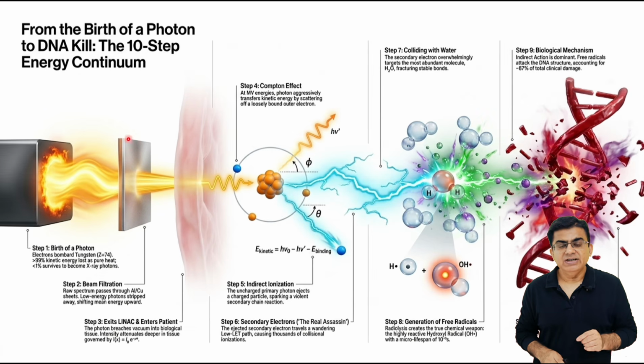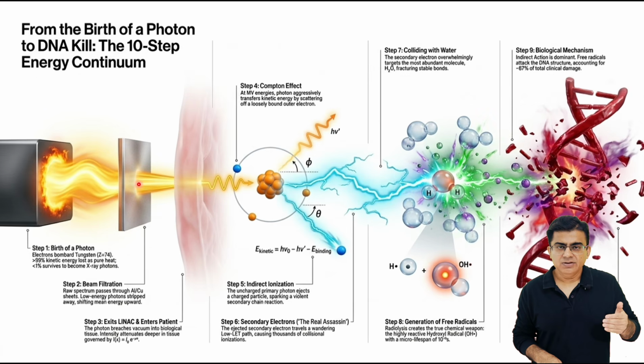Step 2 is beam filtration. The raw and unfiltered X-ray spectrum of radiation is highly useless, rather dangerous. It must pass through filters made up of aluminum or copper sheets. These filters strip away the useless low energy photons, shifting the mean energy of the beam upwards.